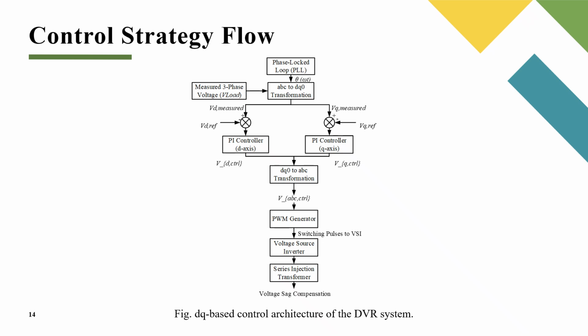These outputs are then transformed back into ABC frame using inverse Park transformation. Finally, the resulting signals are fed into a PWM generator, which produces the gating signals to control the inverter switches. This sequence ensures that the DVR injects the appropriate compensating voltage quickly and accurately whenever a disturbance occurs.